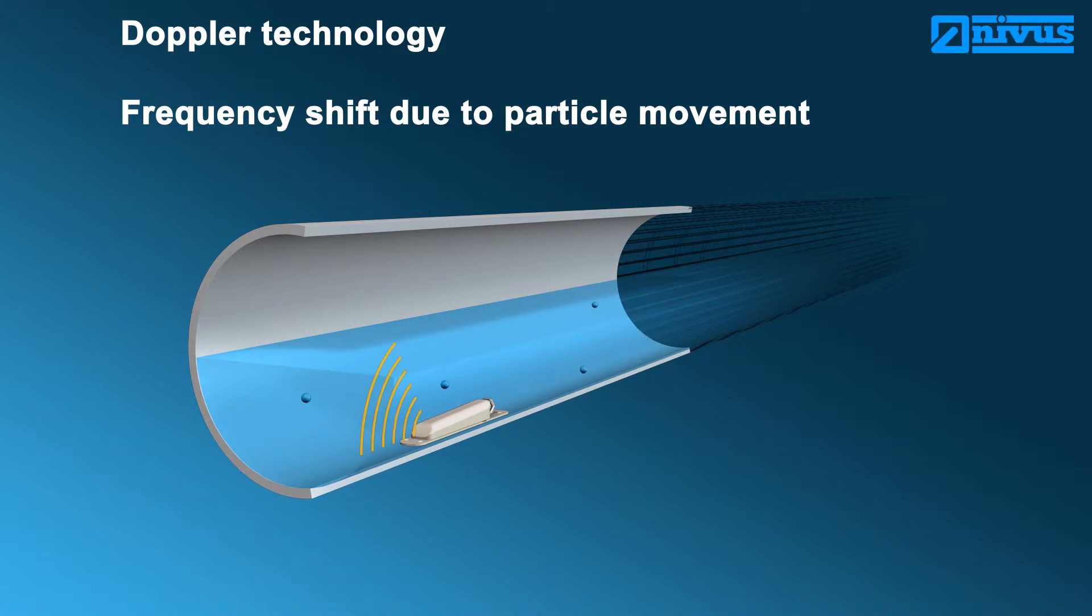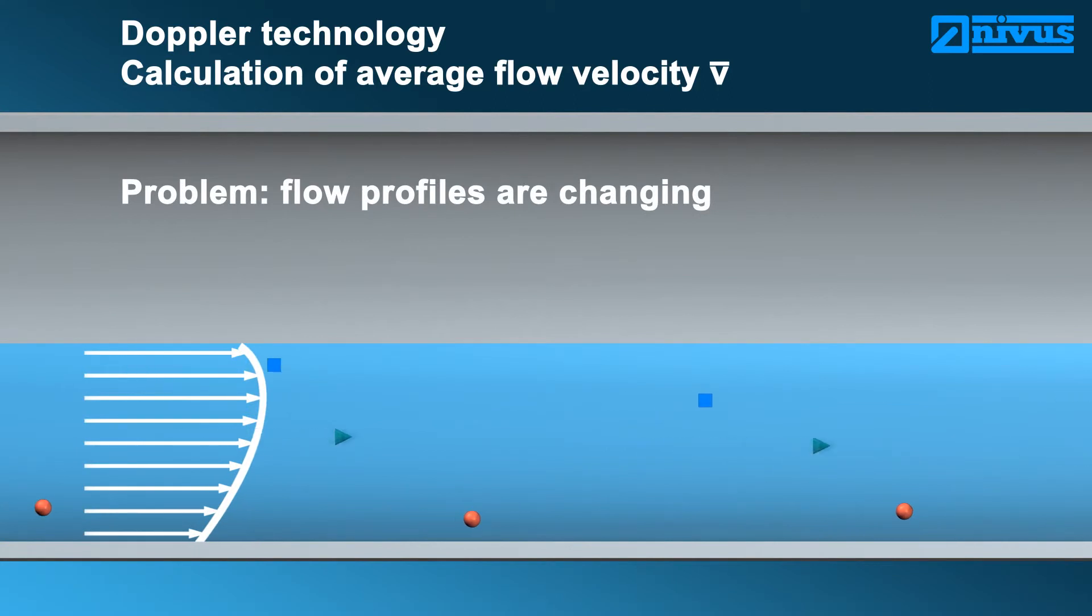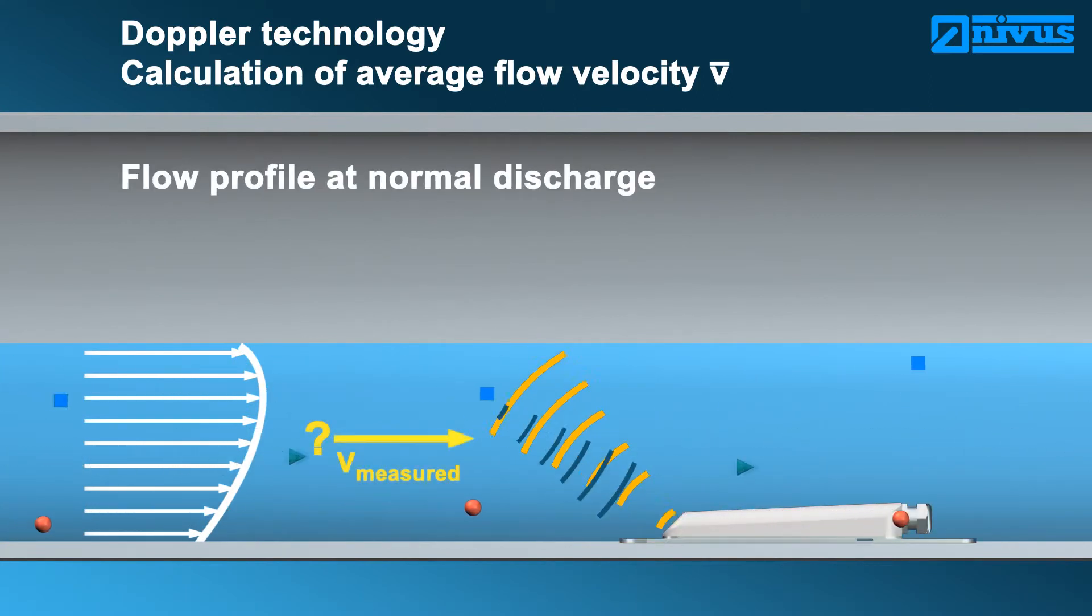The frequency shift is detected by the sensor. The greater the particle velocity, the greater the frequency shift. Doppler measurement is a spot velocity measurement. The sensor is not able to determine at which level the velocity has been detected. Due to this reason, the flow profile cannot be represented.